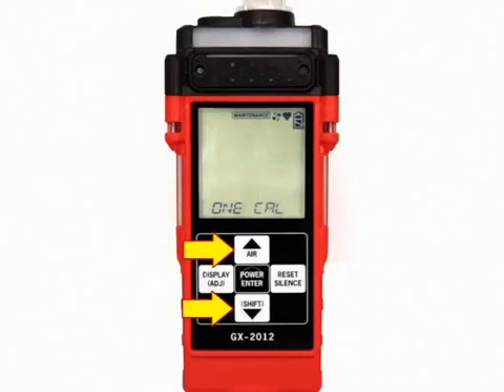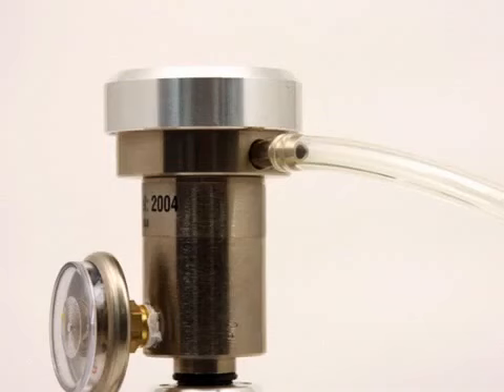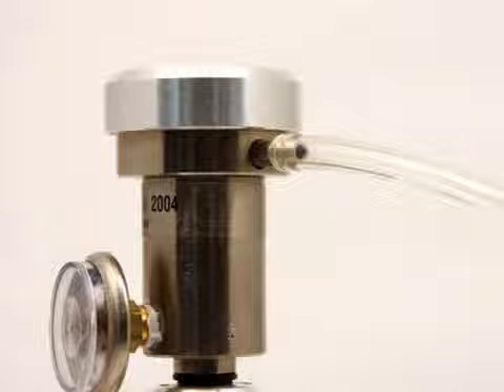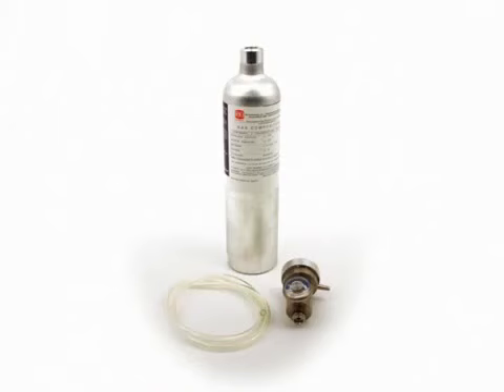Use the air and shift buttons to scroll to escape in the 1 cal menu. Press and release the power enter button to exit 1 cal. Remove the regulator from the calibration gas cylinder. Store the components of the calibration kit in a safe and convenient place.